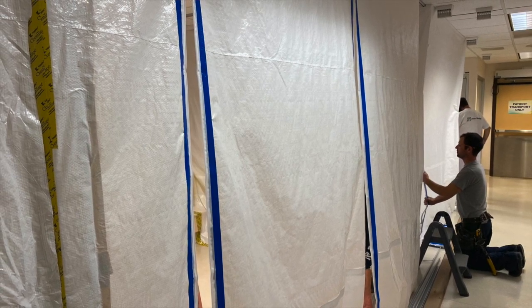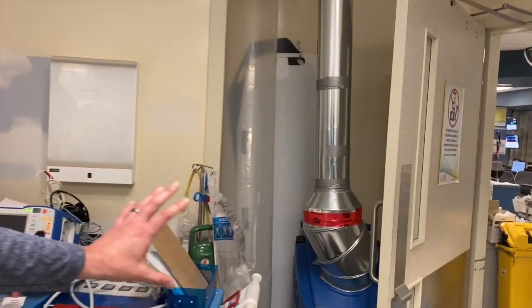Now we're in the emergency department. These three rooms were created specifically for COVID patients coming in through Emerge. Over the course of the last couple of days, we've added negative pressure in these rooms. We've put this filter in place, which is pulling air out of the rooms through the ductwork across the ceiling and filtering it out of the building.